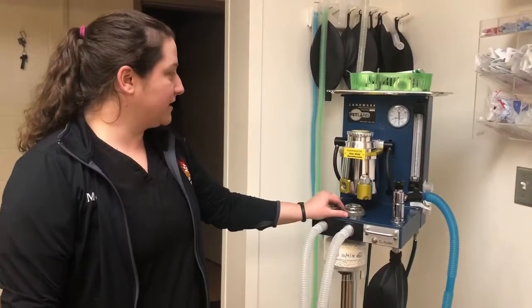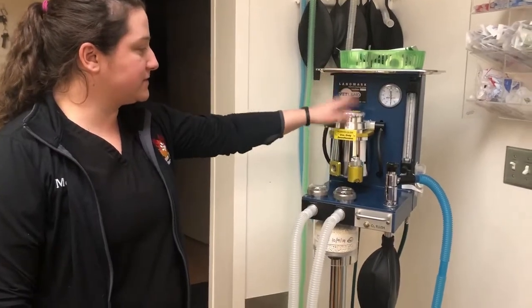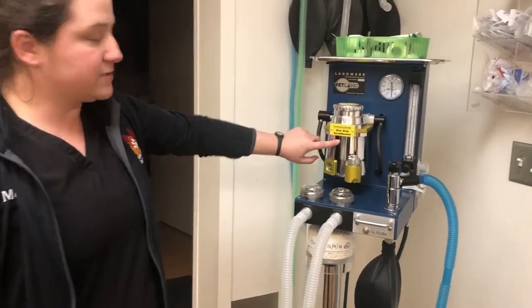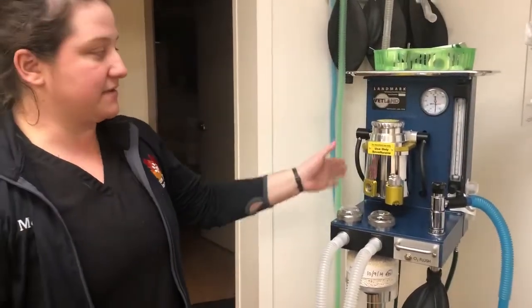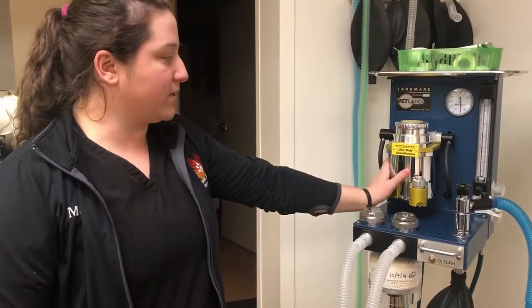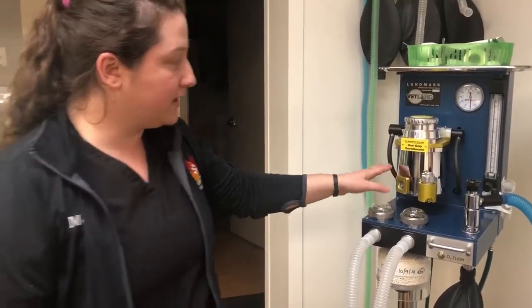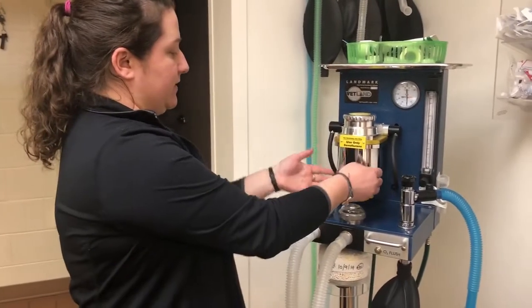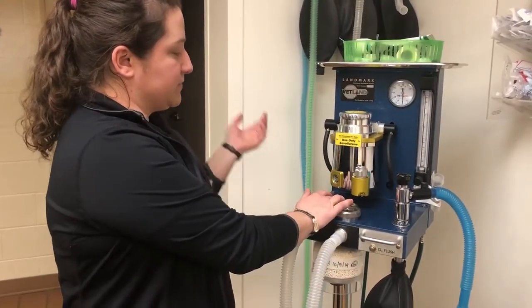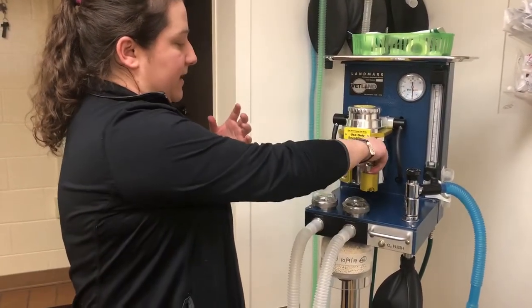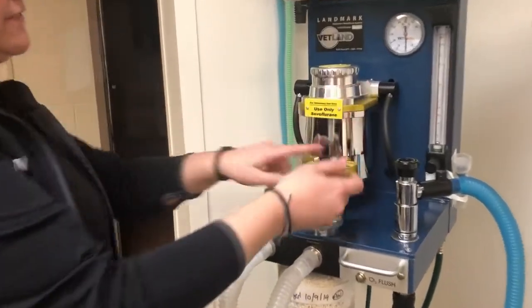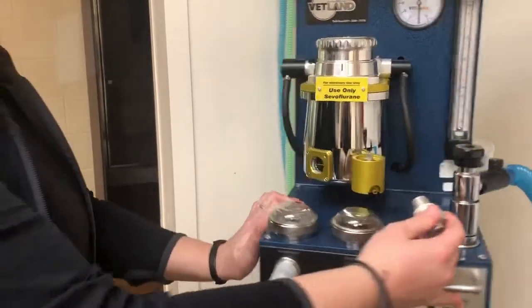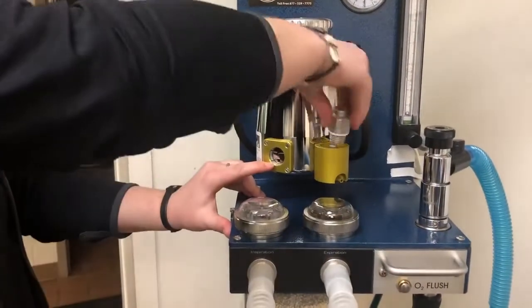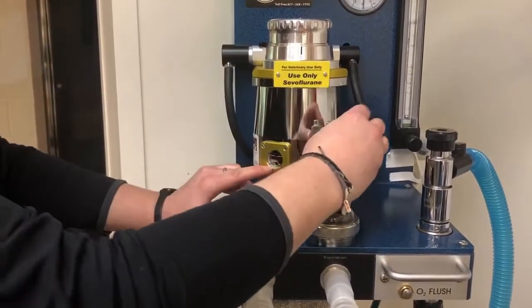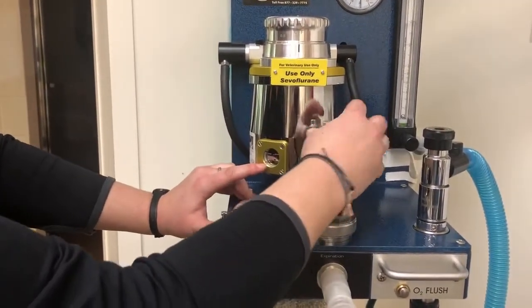So this is our anesthesia machine. We use sevoflurane. In this machine, we also have another machine that's exactly the same, but has the vaporizer for isoflurane only. So this is the vaporizer unit, converts the sevoflurane into the gas inhalant. And you just fill right here in this reservoir.